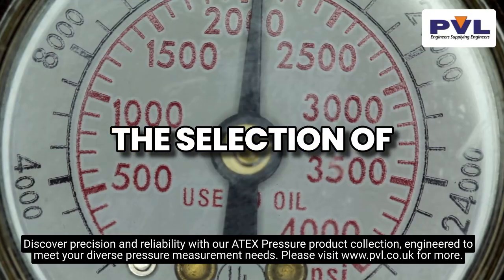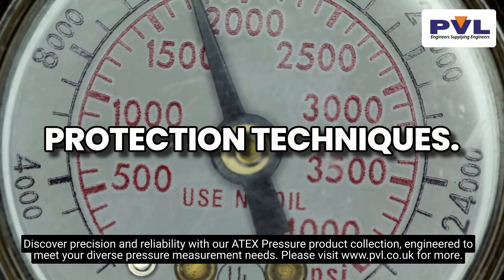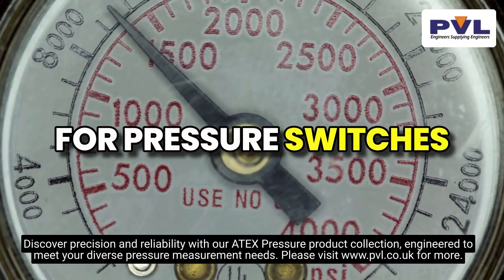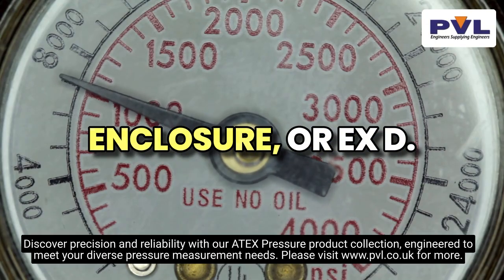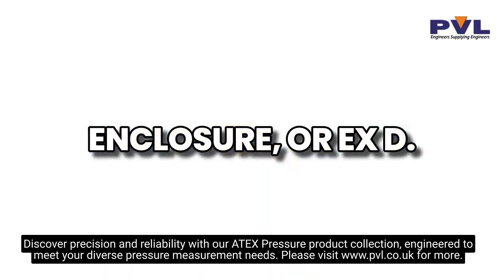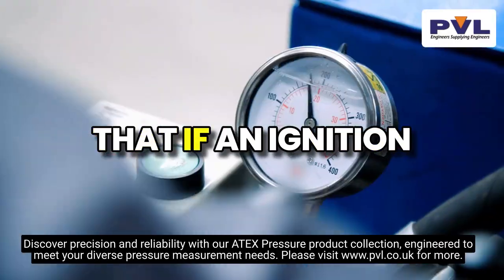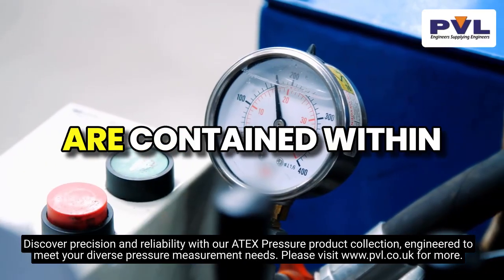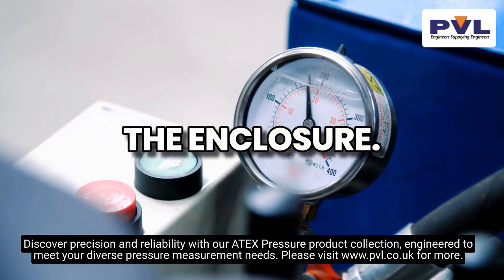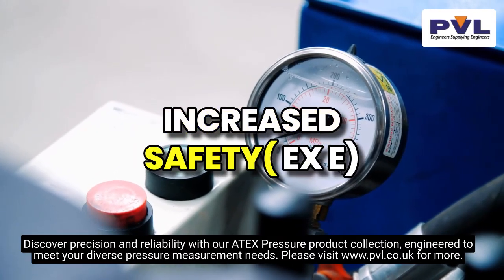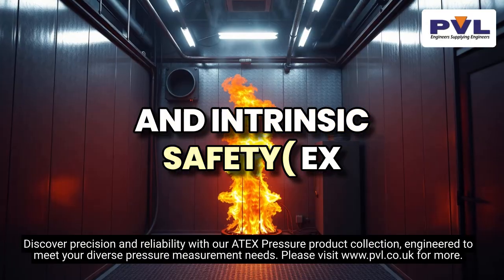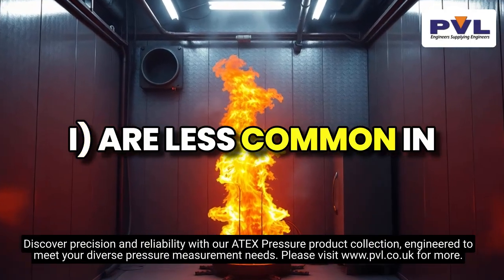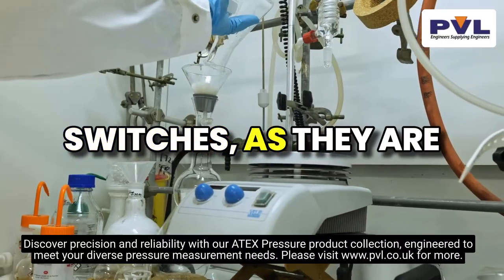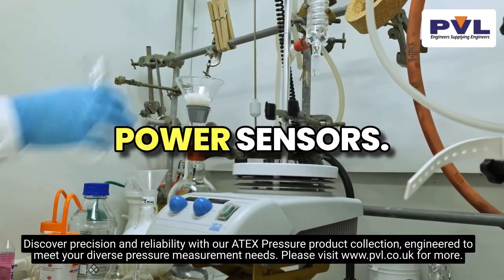Next, we need to consider the selection of protection techniques. The most common method for pressure switches is the flame-proof enclosure, or Ex d. This technique ensures that if an ignition occurs, the flames are contained within the enclosure. Other methods like increased safety, Ex e, and intrinsic safety, Ex i, are less common in mechanical pressure switches, as they are typically used for low-power sensors.